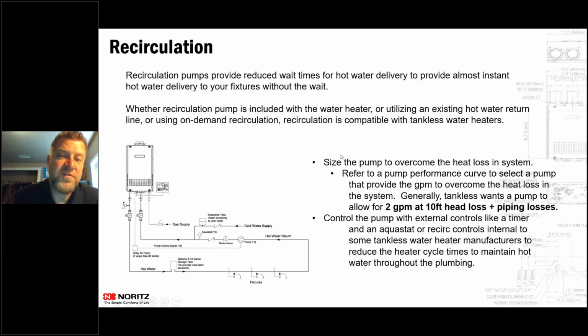So recirculation, we do have units that have recirculation pumps built into them. If you are adding recirc to a unit that does not have a recirc pump, we make a little kit that has a Grundfos pump, but it connects into the unit. The unit controls the pump. It's pretty cool. But if you are adding an external pump to any tankless water heater that's out there on the market, first of all, make sure you're adding an expansion tank to the system if you are going to be adding recirc to it.